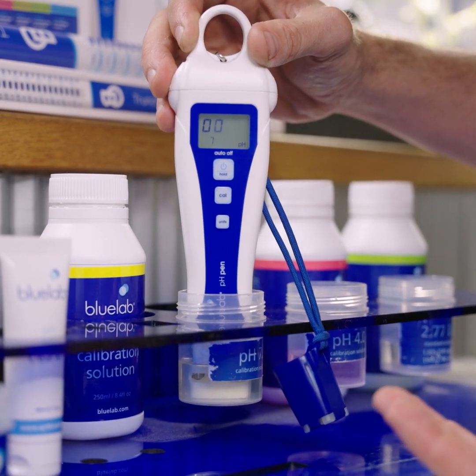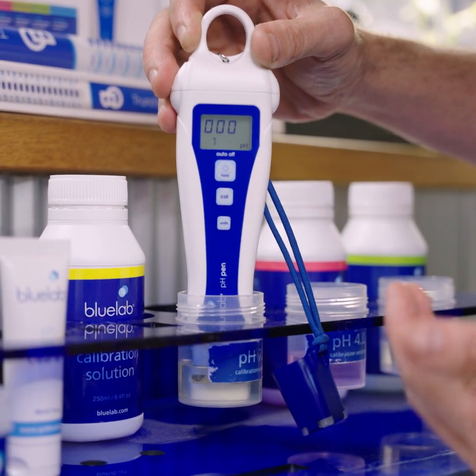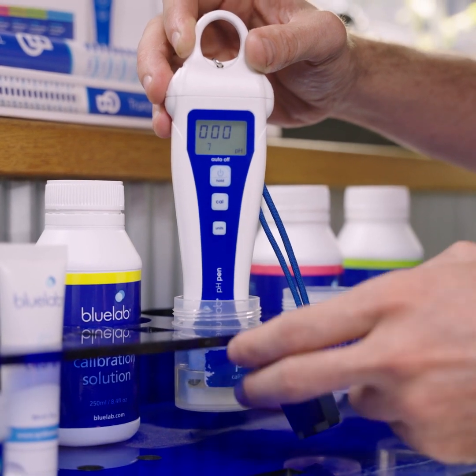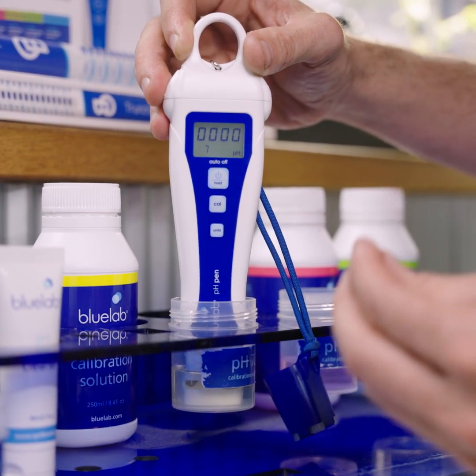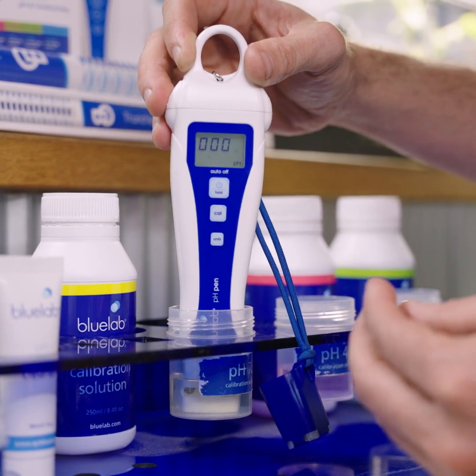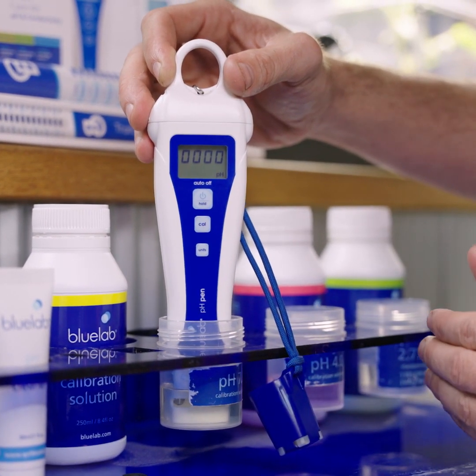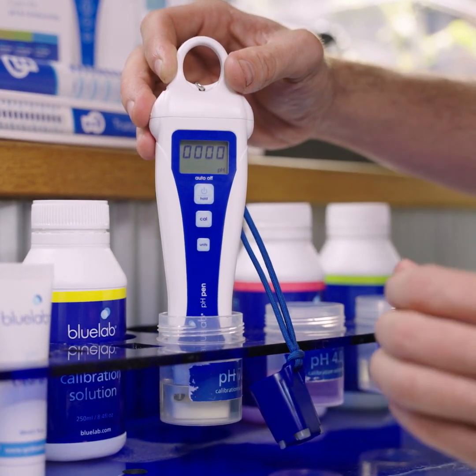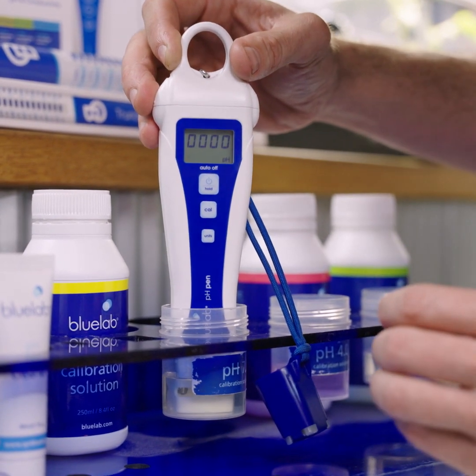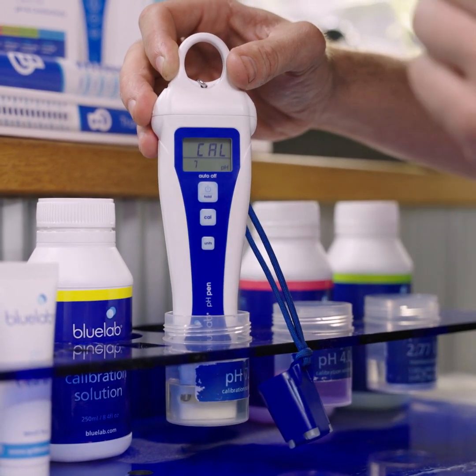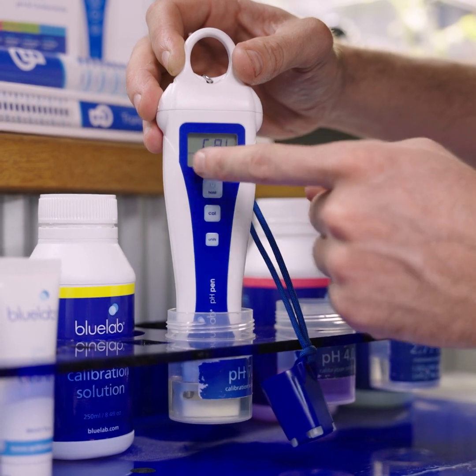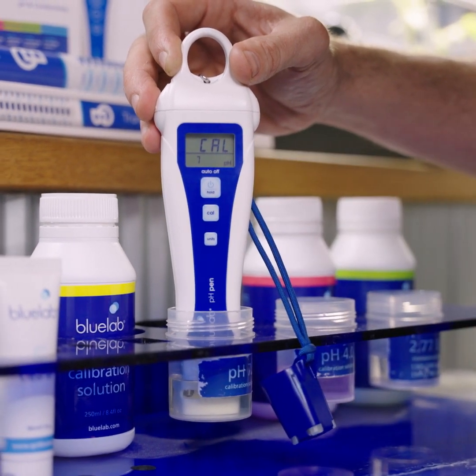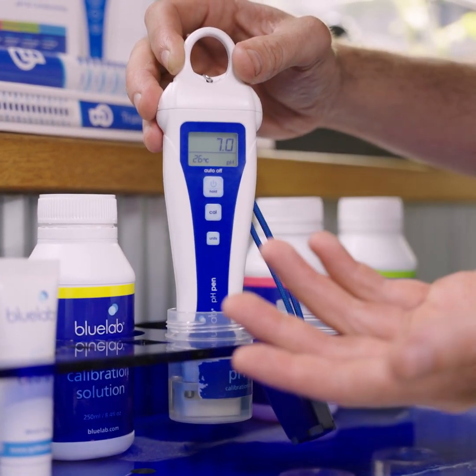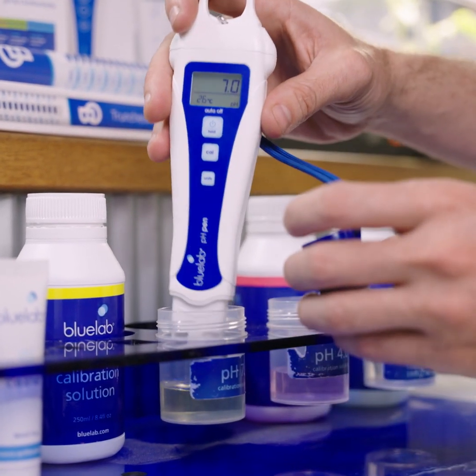What we're doing here is we're basically forcing the pH pen to recognize that this solution is a pH of 7. So the solution pH 7 and pH 4, that's all they are. They're a solution that is exactly that pH. So when you calibrate it, you're saying this is 7. So now it says calibration 7, there's no error. It should go back to normal. So then that should read 7.